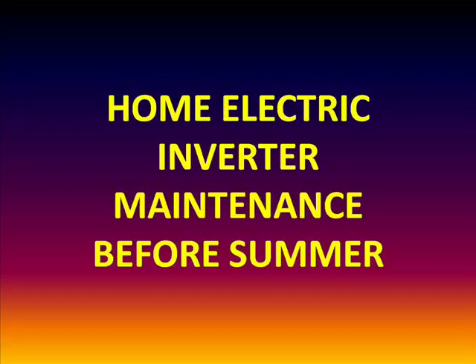So if you buy a 150 Ah battery, and you put 4 tube lights and 3 fans, it must support continuously for 3.5 hours. But practically it is not so. The reason is that modern batteries are not capable of being fully charged by the inverters. At the most it charges a maximum of 100 to 120 Ah. So it supports only 2 hours.